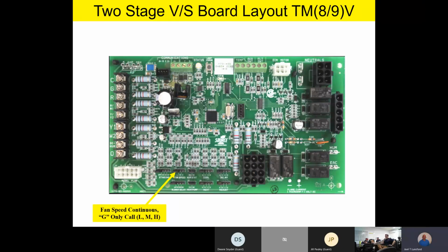Again, it's going to look at your cool and adjust jumper to see how much your high-speed cooling airflow is, and then high, medium, and low is going to give you a percentage of your cooling airflow if you have a G-only call. Again, low's 50%, medium's about 65 to 70%, and high is 100% cooling airflow. So that gives you some nice little options there. Any questions or comments so far before we talk about the last couple jumpers? Any questions? Everybody good? Okay.